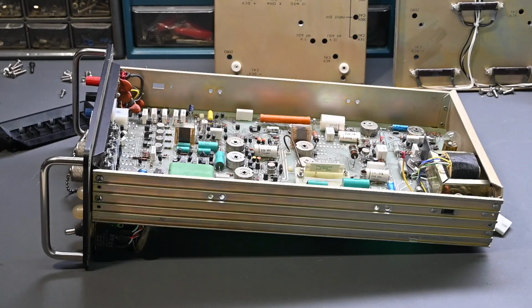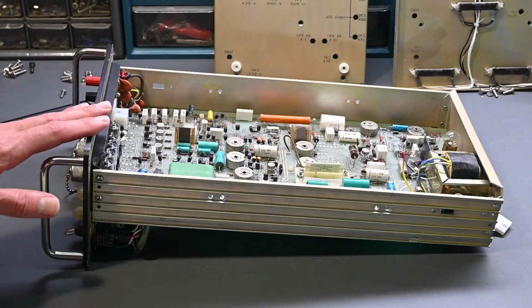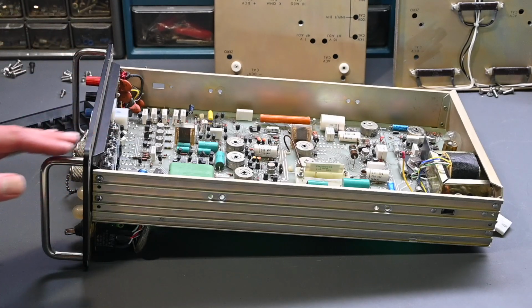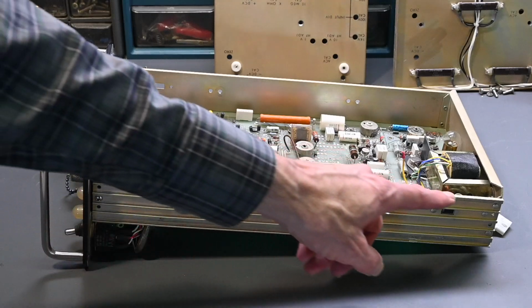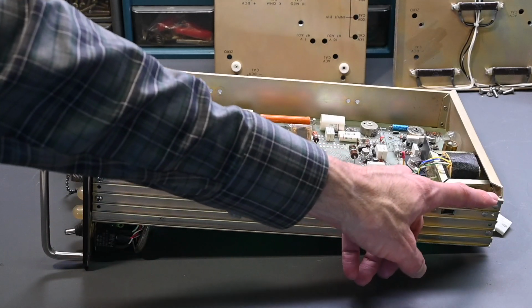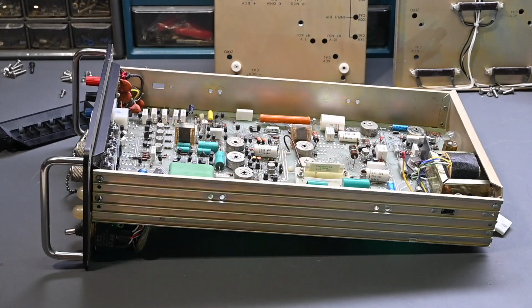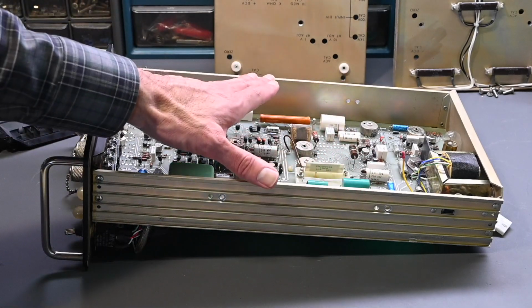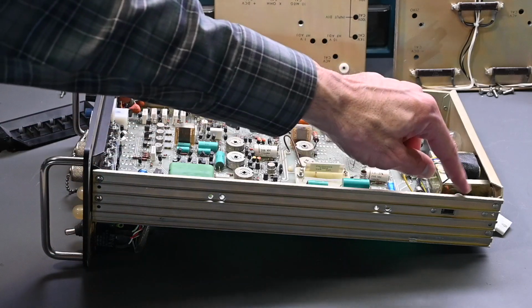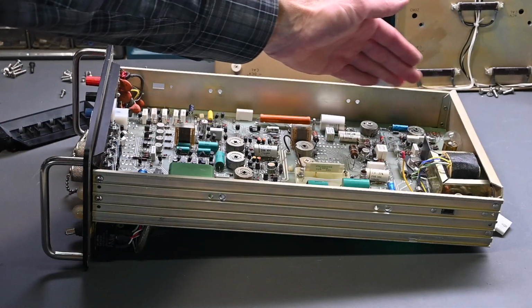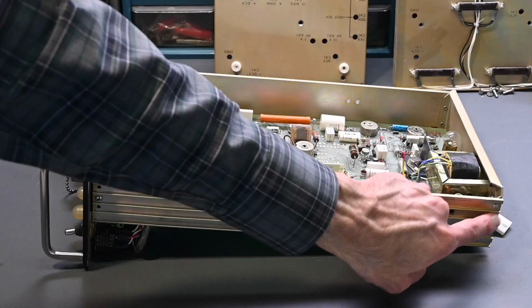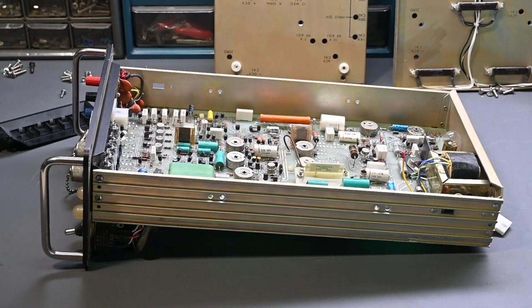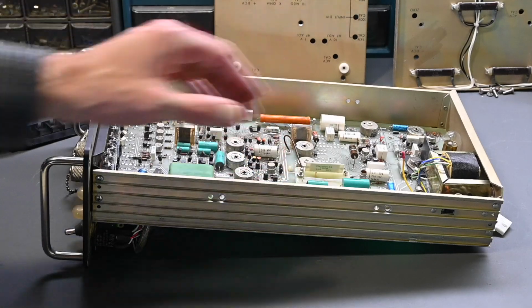So some of the other repairs that I can make are more mechanical in nature. I noticed that the instrument was either dropped or handled very roughly, and I mentioned that in part 1. There was a very noticeable bend on this panel right here in this back corner, and I straightened that out already. I used a press and was able to press it back into position. I didn't need to remove these channels from the rest of the instrument. This side panel and this panel are riveted to this back panel. Rivets in the corner right there, and the rivets are in good shape. They're tight, no problems there. But it saved a lot of work not having to remove all of this from the instrument.